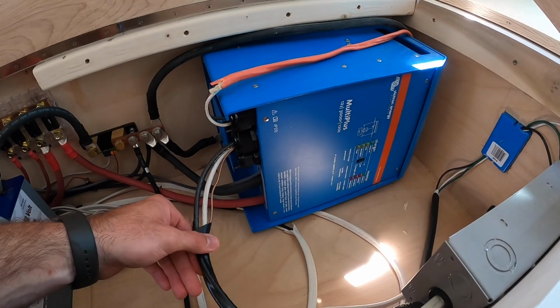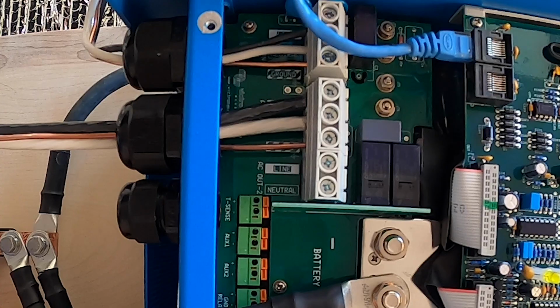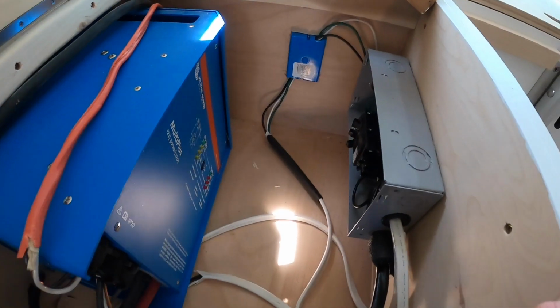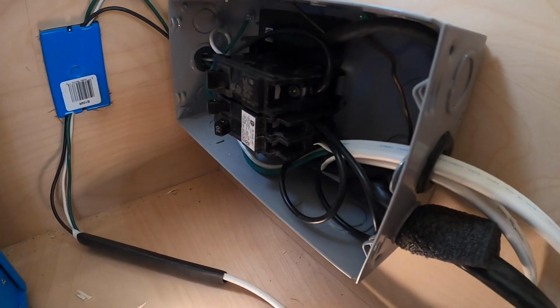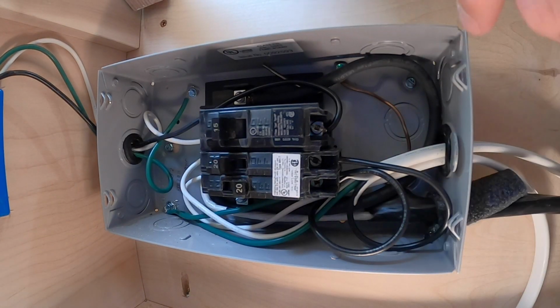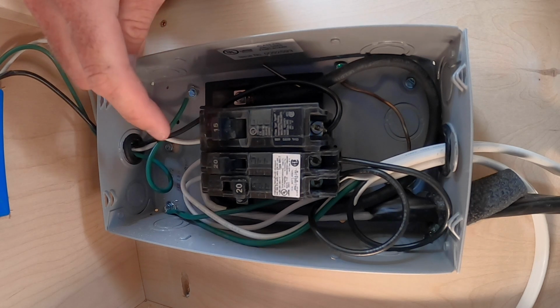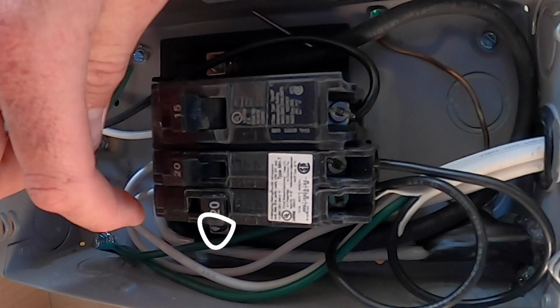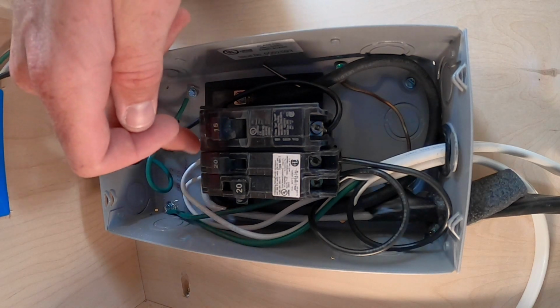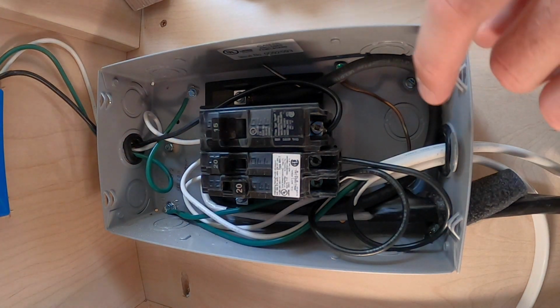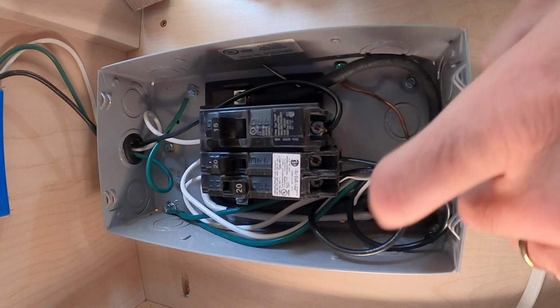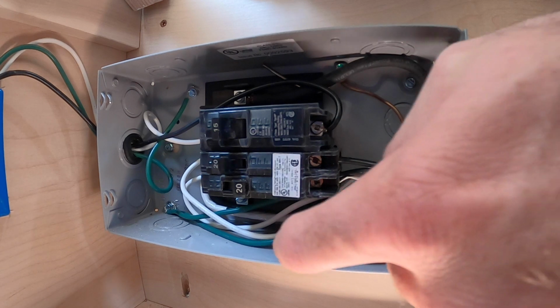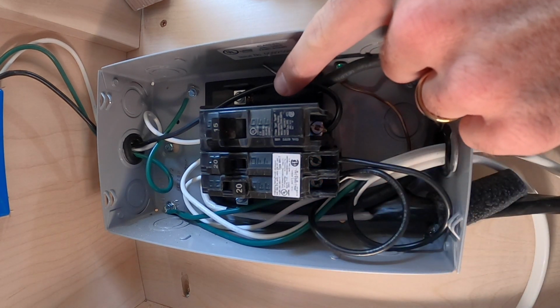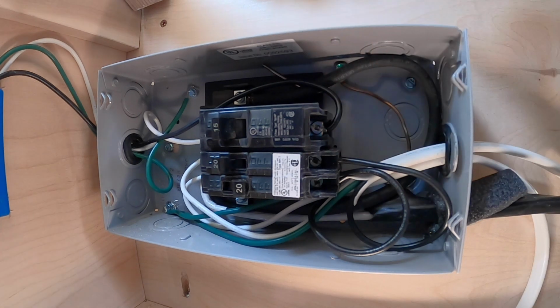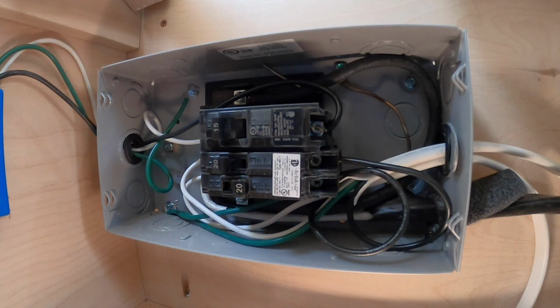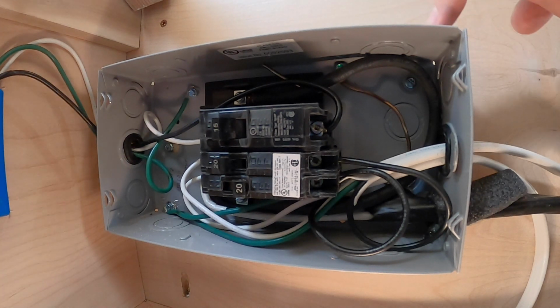And then we have 6-3 wire coming from the inverter into our AC distribution circuit breaker panel. It's connected to the hot connector, and then I have the neutral connected to the neutral bus bar on top. And then I have a jumper cable, 6 gauge wire, connecting it to this hot terminal connection. I don't really know the correct terms. Again, I'm not a professional, so please connect with a professional when doing your setup.